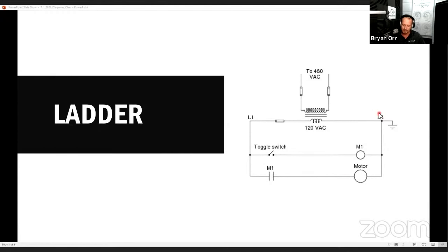Somebody here brings up high voltage and low voltage, series and parallel. Almost everything that we work on is parallel circuits. We can connect switches in series with each other. So we could have a switch and a switch and a switch and a switch, but we're almost never going to put more than one load, which is the part that actually does work, whether it's electromagnetic, which is what we call inductive, or whether it creates heat or light, which is what we call resistive.